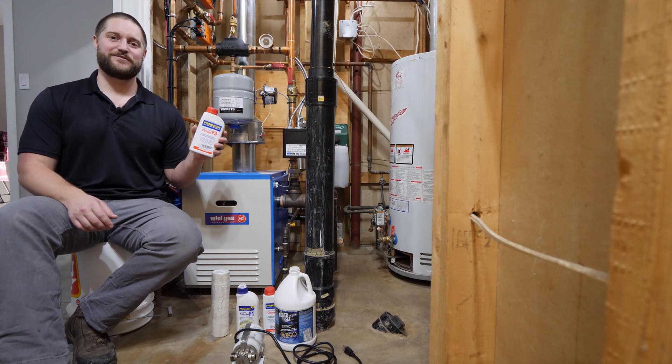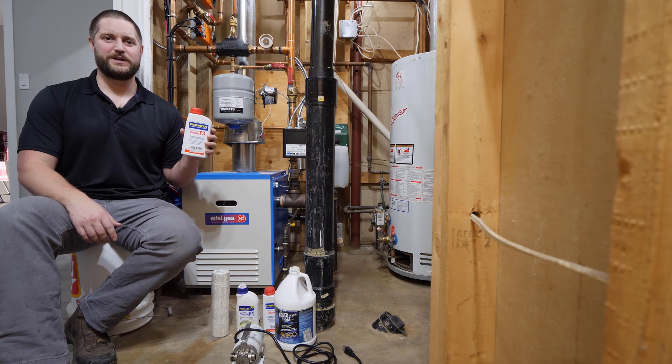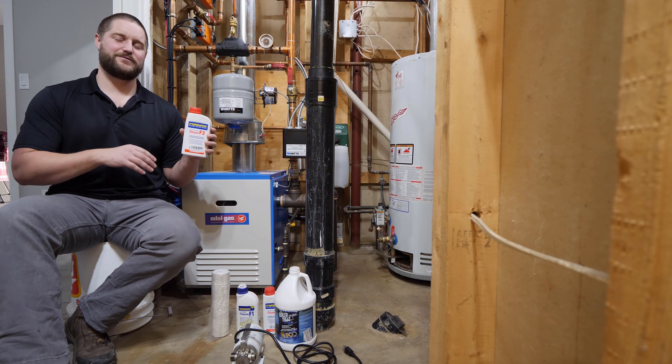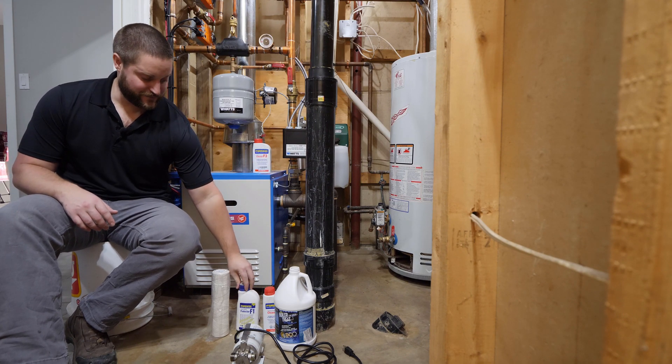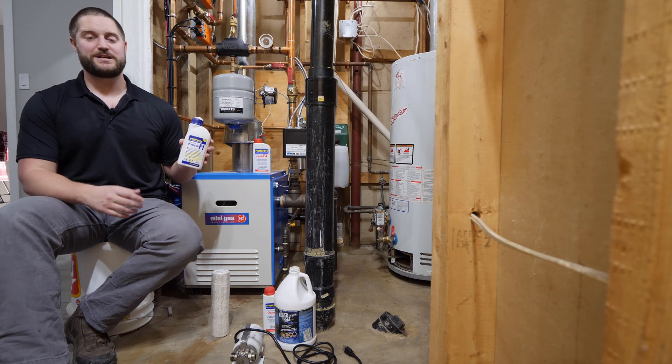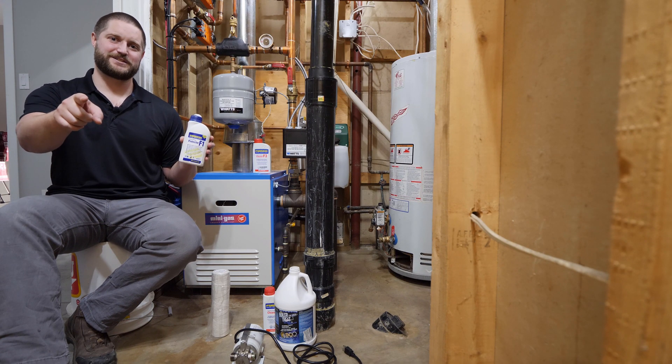After that, I'm going to add some Fernox F3 cleaner. This is a descaler. I'm going to let it soak for about a week, and then I'll revisit it, flush the entire system, and once I refill the system, I'll add some Fernox F1, which is a conditioner and will help reduce the buildup of scale. Let's get started.